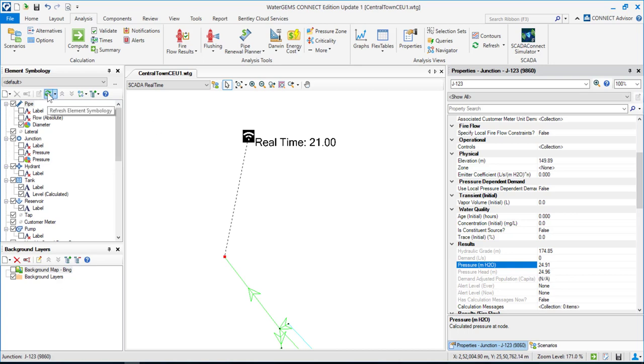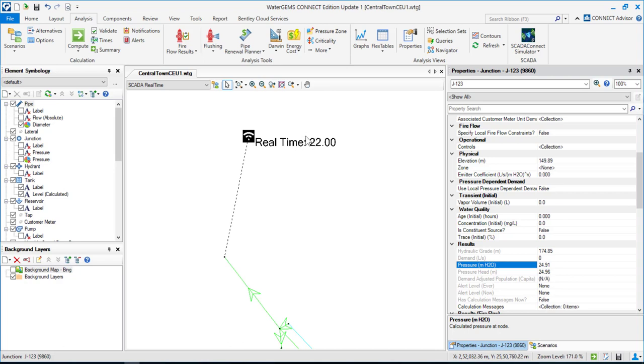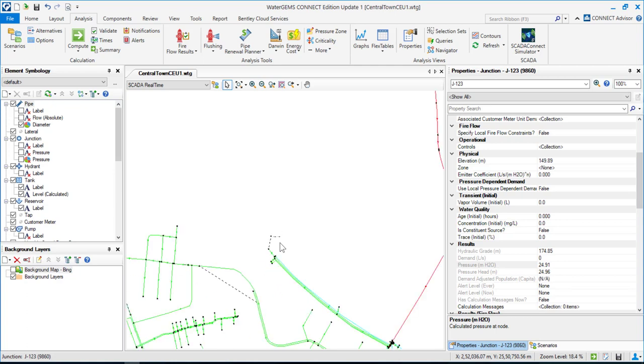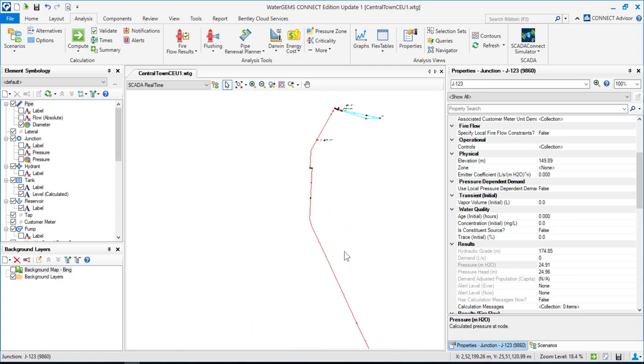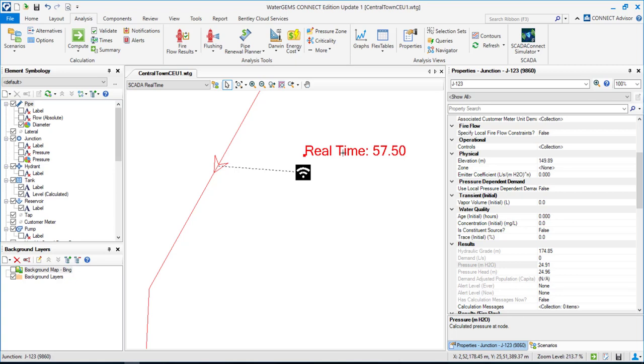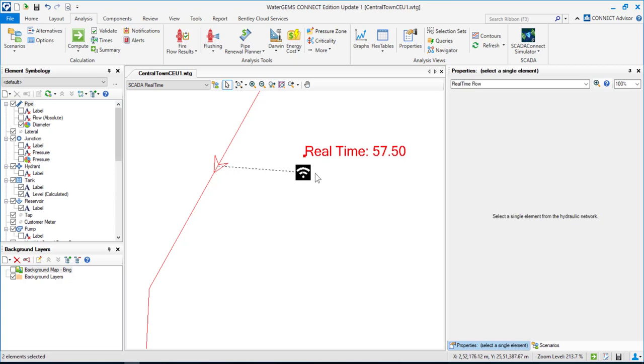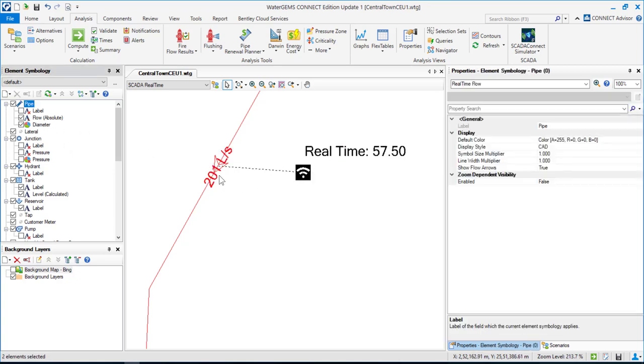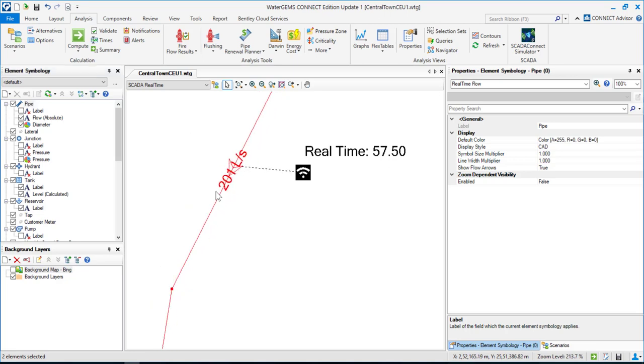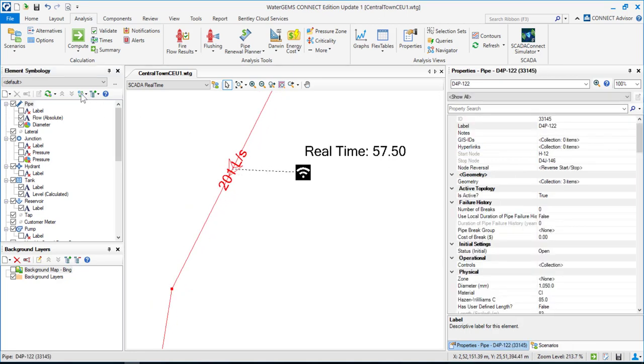If I hit 'Refresh Element Symbology', it refreshes and you can see the pressure has increased. You can have real-time information right inside your hydraulic model. For pipes, for example, the hydraulic model pipe flow is at 201 liters per second, while the real-time pipe flow is only 57.5 liters per second.